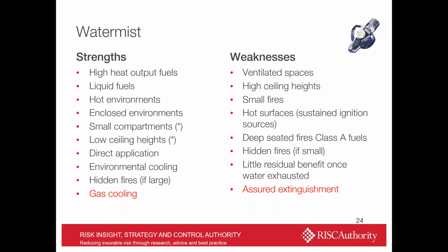The weaknesses, ventilated spaces, as hopefully we've demonstrated there. You can cross a threshold so that a lot of the benefit disappears all too quickly. High ceiling heights, we said before, where the momentum of the droplets gets lost with distance. Small fires can remain remarkably resilient against Watermist systems, because they don't have the energy to drive the circumstances for their own demise. They're not necessarily very good at cooling hot surfaces, not necessarily very good on deep-seated fires in Class A type fuels, which, again, as we know with sprinkler systems, might require wetting the fuels.